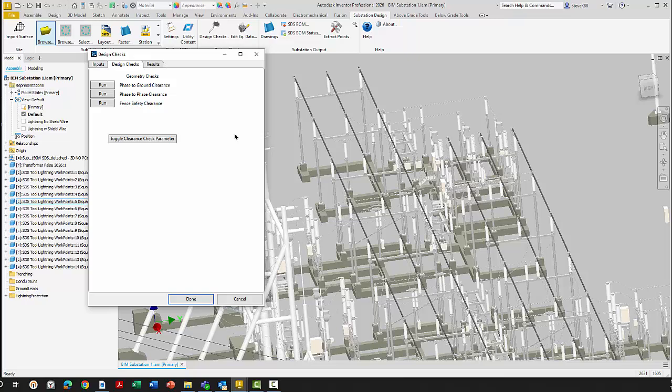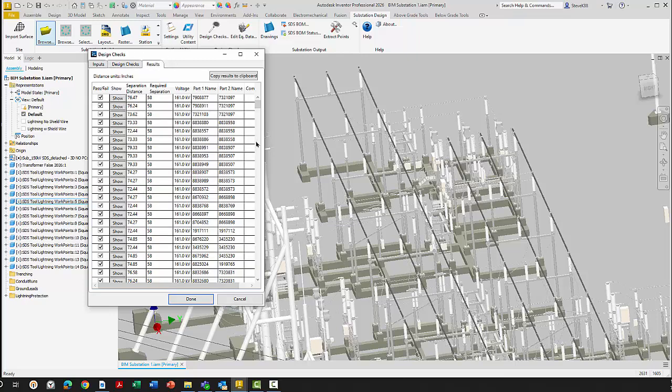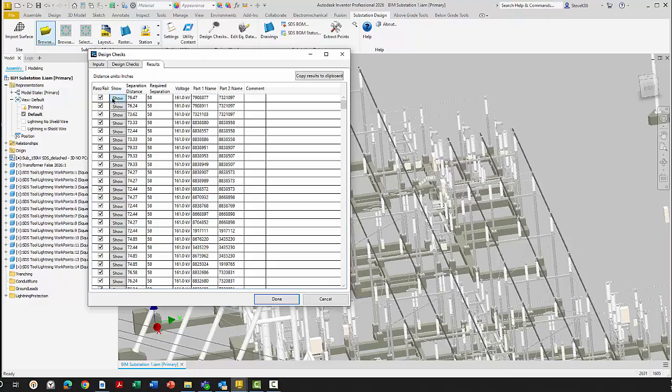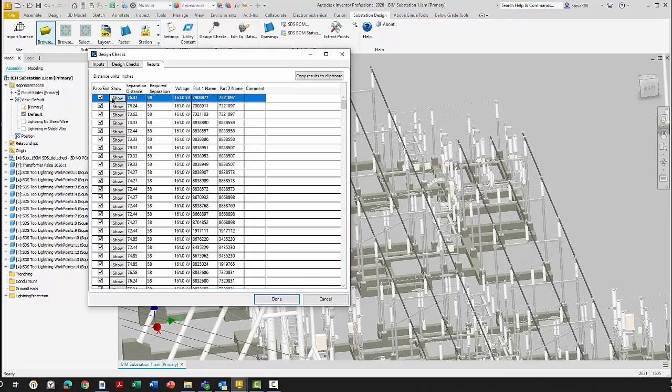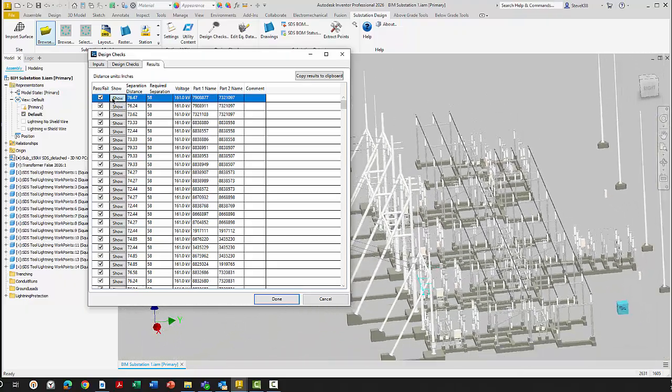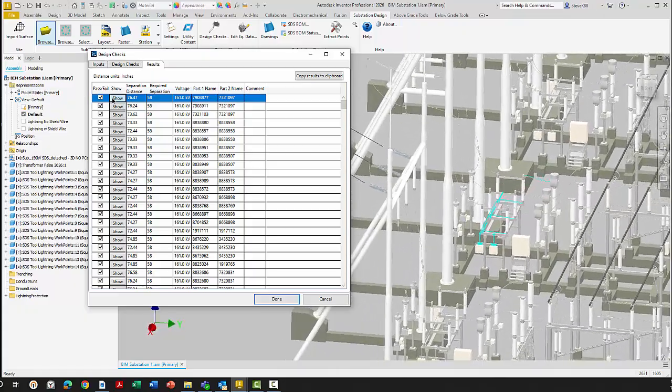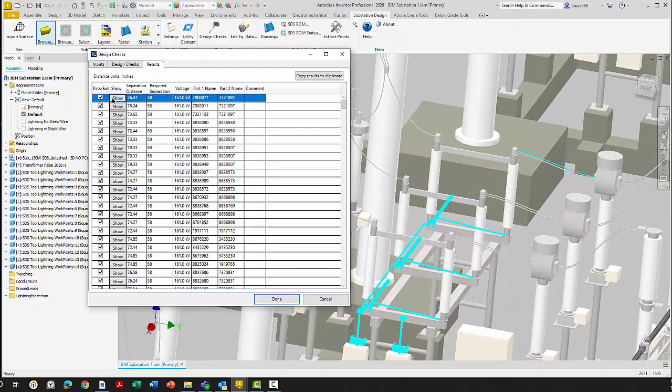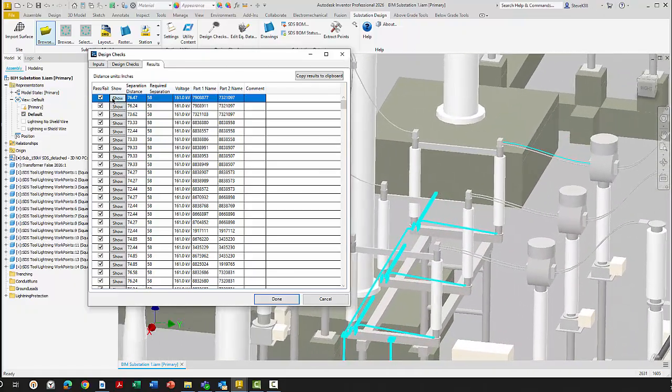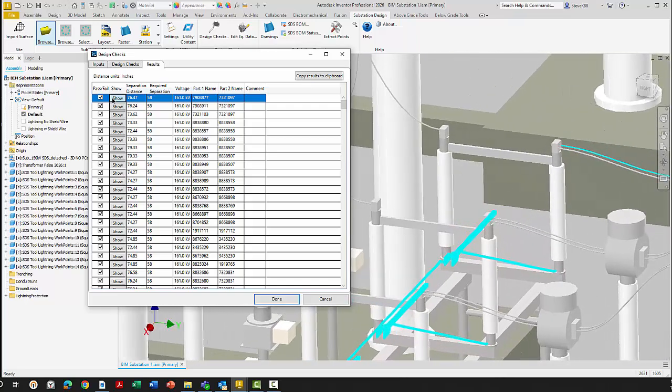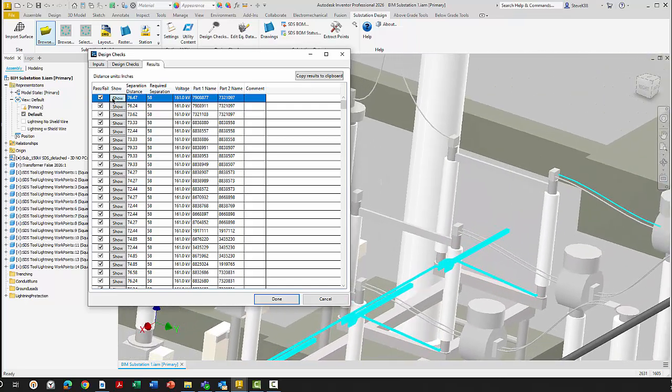The phase to ground check was completed. We'll go look at the results. I'll expand the results and we can sort the results. We see the two part names that were checked. We see the voltage level that it was checked based on. And we see the separation required. If I go show on the first one here, we should be able to see what two items were checked. It's the cable to the switch mechanism there. And it's 76 inches and the minimum required is 58.